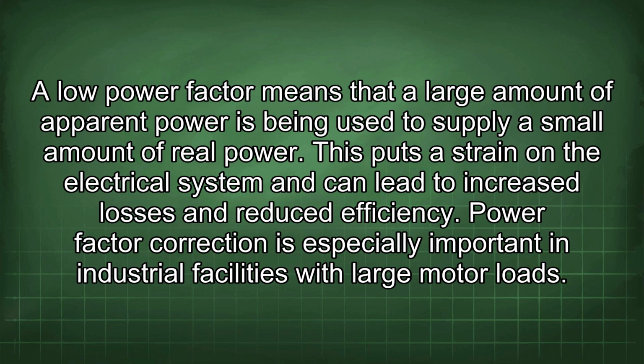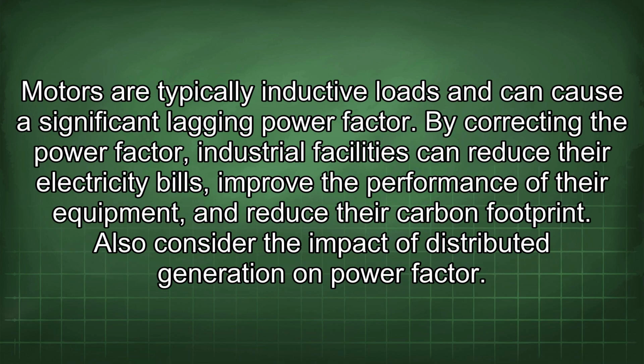Power factor correction is especially important in industrial facilities with large motor loads. Motors are typically inductive loads and can cause a significant lagging power factor.